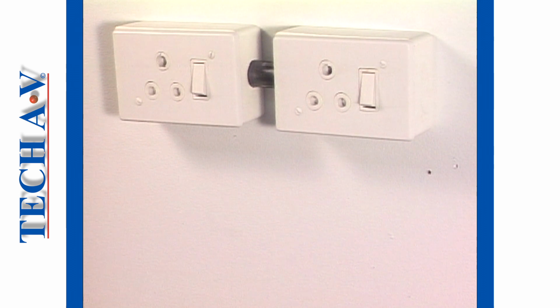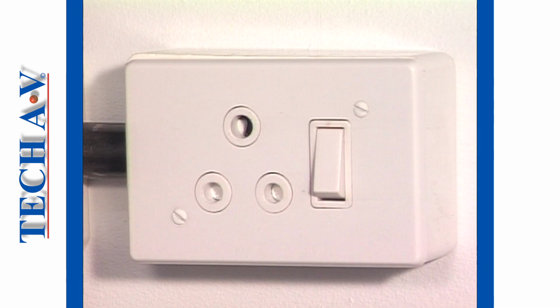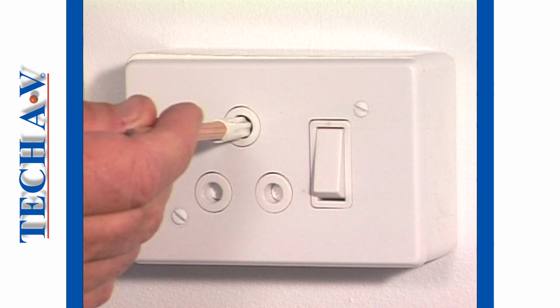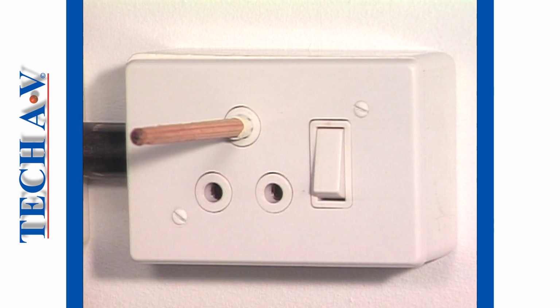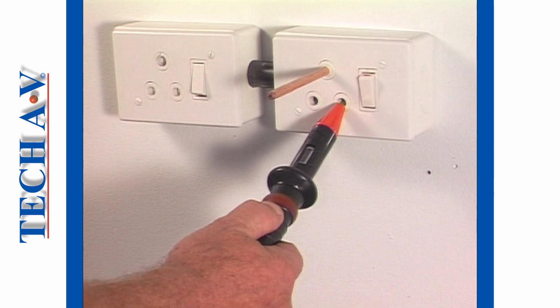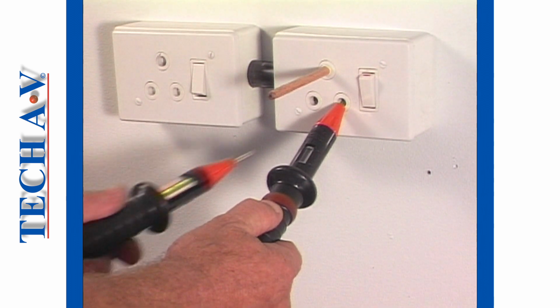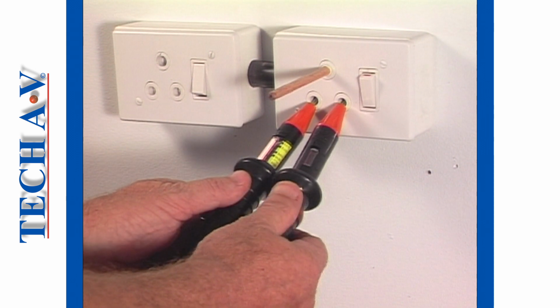Let us demonstrate the tester application in a typical 3-pin socket outlet, which we shall assume has been wired correctly. If the socket has a protection shield, insert a non-metallic probe into the earth socket to open the live and neutral sockets, then switch to the on position. Insert the neon probe point into the live socket, that is the right-hand socket from your point of view. The voltmeter probe is inserted into the neutral socket.